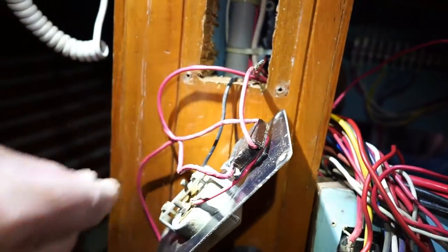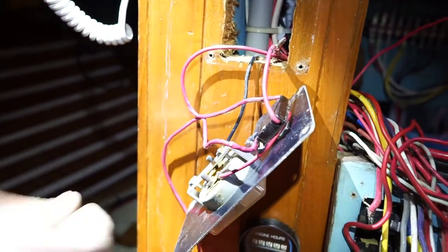There's a chunk of wood — somebody intentionally electrical-taped it to the inside of that selector switch. All the insulation is ballooned on this wire — it's just melted and gotten bubbly.